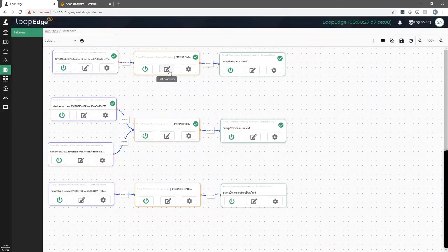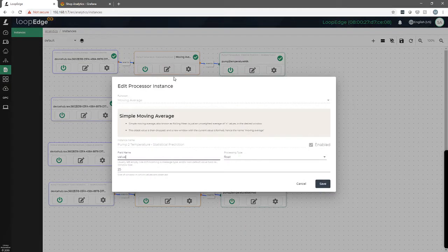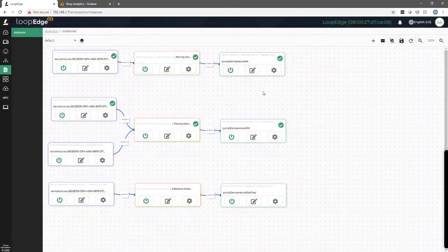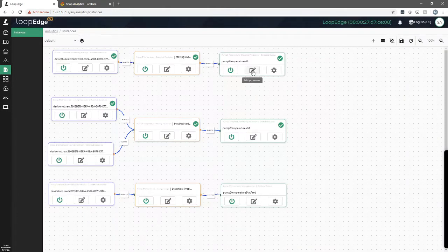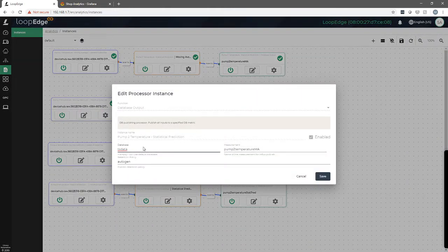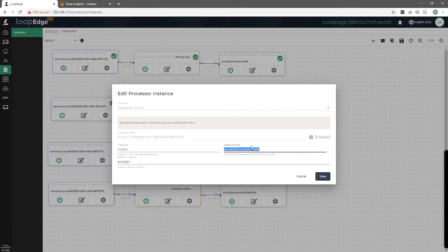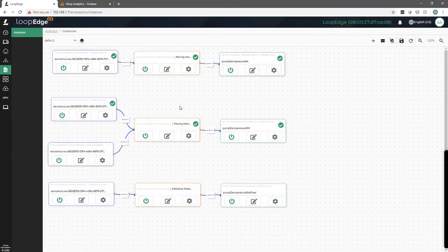The second piece is the function, and here if we look inside we're doing a simple moving average and we're taking the last 25 values that we've read and performing a simple moving average on that. And here on the output portion you can see we're writing it to a database. It's TS data which is our default database and we're giving it a name inside that database called pump two temperature MA for moving average. And that's it. Those are the three different pieces.